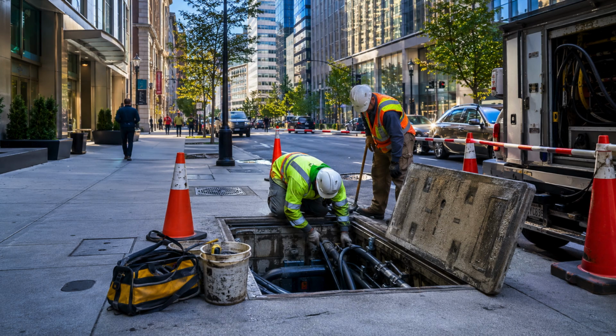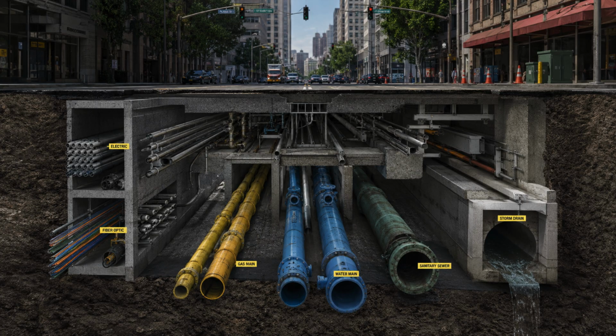That is very different from taking an existing neighborhood with overhead wires and converting it to underground service after the fact. Retrofitting an older neighborhood is expensive and disruptive. Crews may need to trench along streets, sidewalks, lawns, and driveways. They may need to avoid water mains, gas lines, sewer pipes, telecom cables, storm drains, and other underground utilities. They may need to install ducts, vaults, handholes, transformers, switches, and new service connections to each customer.